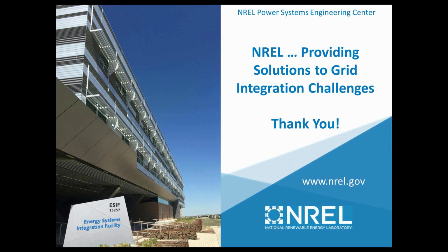In your opinion, how much reactive power mismatch can rule out islanding, Sandia screen 3 and 4, even if reactive power match is very low? It oftentimes depends on what kind of distributed generation device you have there. In a lot of cases, if it's a synchronous generator, and this actually ends up being true for inverter-based also, you have to look at what the reactive power capability and settings are inside the island. So it's tough to make a determination here without knowing that.